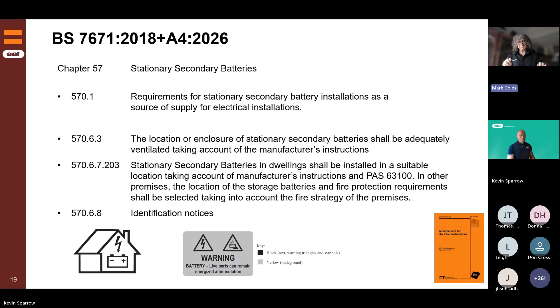The last one, 570.6.8, is about identification notices. If you've got batteries installed, you need stickers on the consumer unit and at the battery, so when somebody comes in to amend something, like working in the kitchen adding sockets, they can see there's a battery system and know they need to isolate in a few different places, potentially.